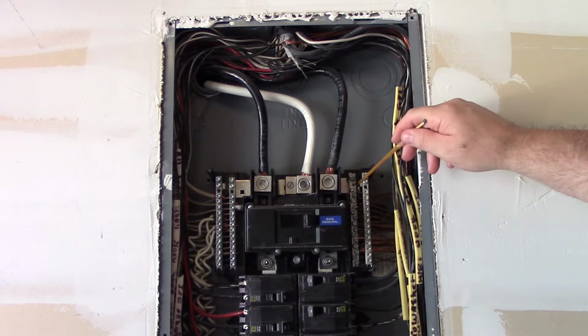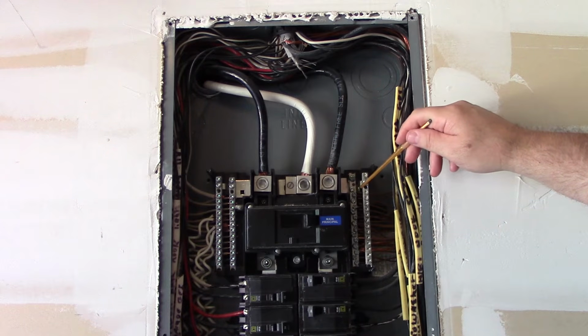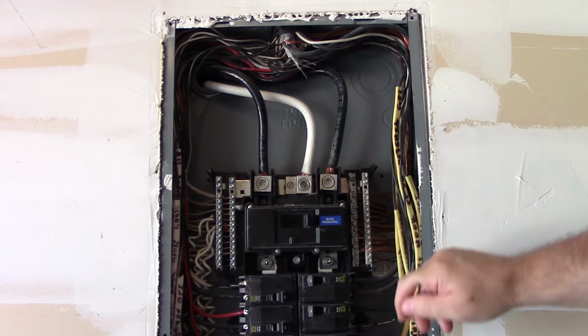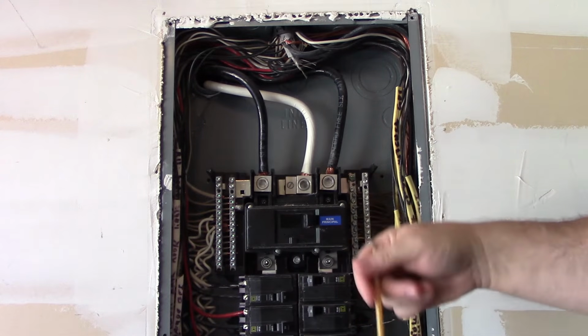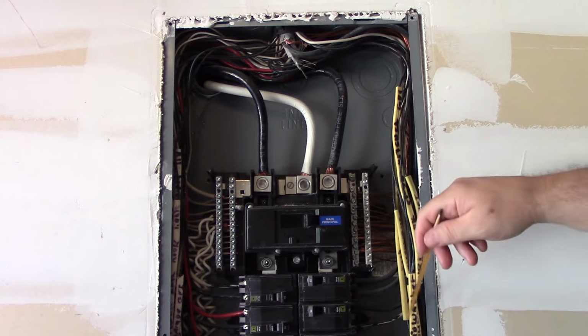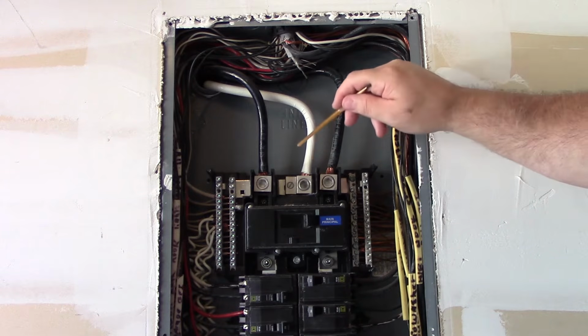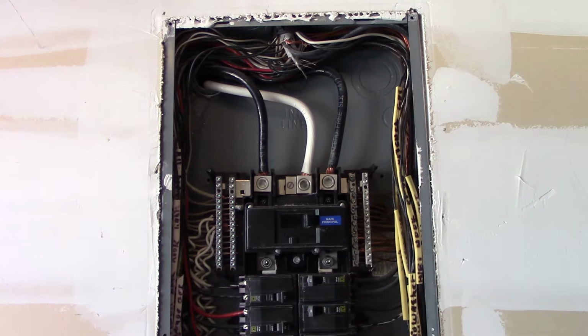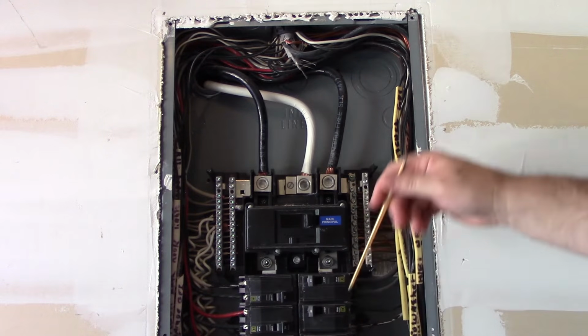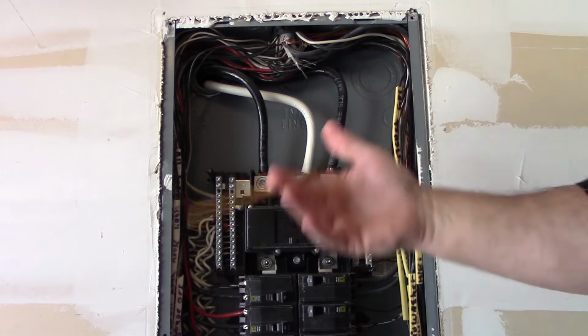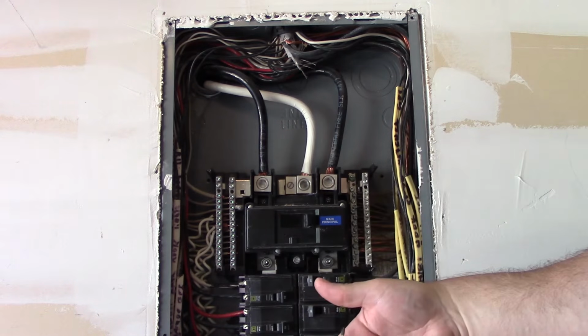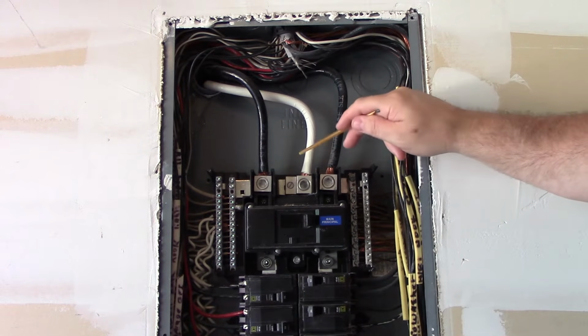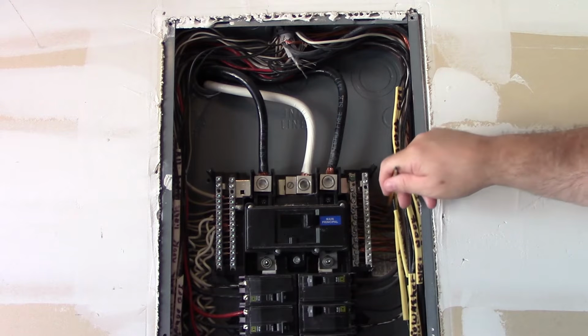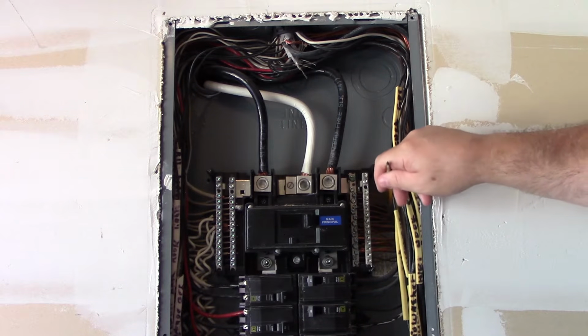Also, we want to make sure that our grounding electrode conductor, or our GEC, which is what's running down here, that's going out to a ground rod, and in this case, a UFER ground, we want to make sure that they connect to the grounded conductor. And that is required by 250.24(A) of the National Electrical Code. So that is done here. But remember, on a remote distribution panel, that grounding electrode conductor does not connect to the grounded conductor. It connects to that separate equipment grounding conductor bar that you ran.